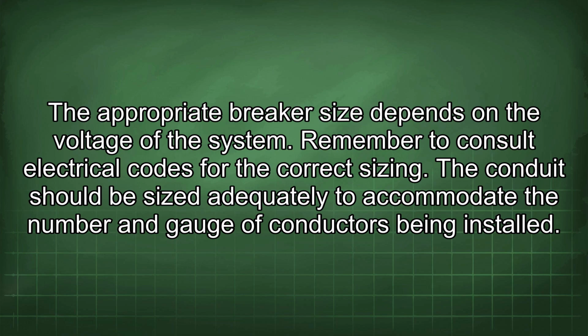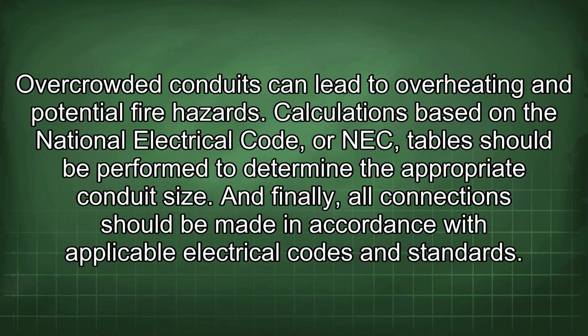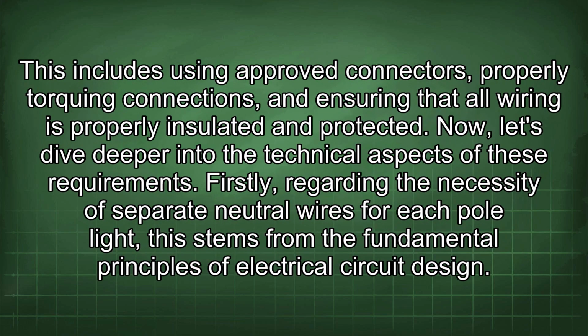The conduit should be sized adequately to accommodate the number and gauge of conductors being installed. Overcrowded conduits can lead to overheating and potential fire hazards. Calculations based on the National Electrical Code (NEC) tables should be performed to determine the appropriate conduit size. And finally, all connections should be made in accordance with applicable electrical codes and standards. This includes using approved connectors, properly torquing connections, and ensuring that all wiring is properly insulated and protected. Now let's dive deeper into the technical aspects of these requirements.